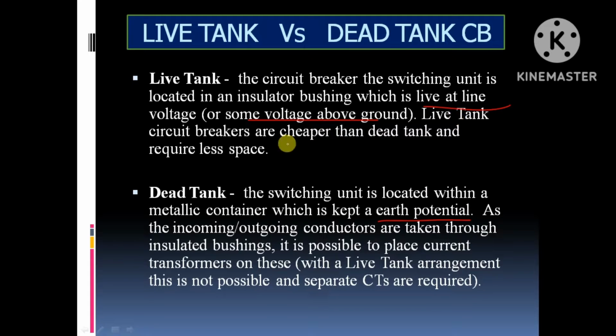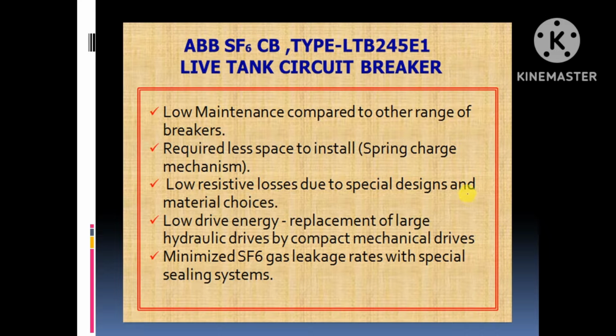And live tank circuit breakers are cheaper. Cost wise, it is very cheap compared to the dead tank. It requires much less gas compared to dead tank, and it also requires very little space, whereas dead tank occupies more space. These are the advantages of live tank circuit breakers. It requires very low maintenance, less space, and it has low resistive losses and low drive energy.